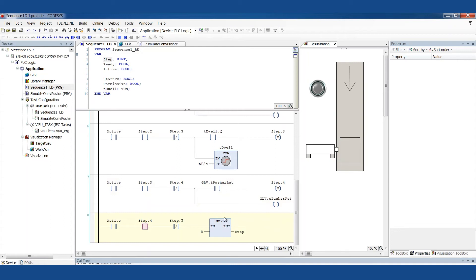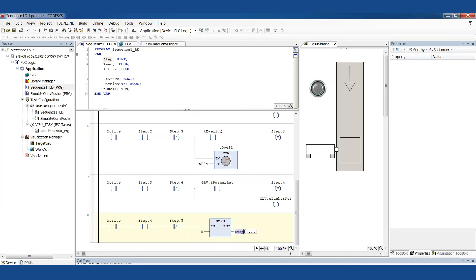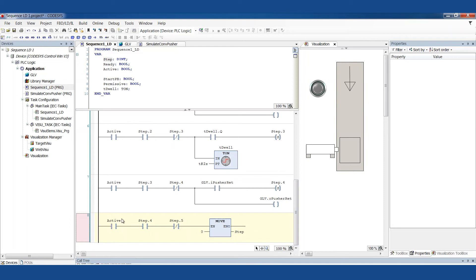In step four, this is another special rung. We're just clearing out the sequence. At the end of the sequence, at some point, we have to say that the sequence is done. We have to clear all of these step bits because we've just been setting them. We haven't been resetting them. The move instruction is assignment. It means I'm going to take this thing and put it into this thing. I'm going to set step to equal zero. And that means we're also clearing out all these bits because all these bits are part of step, that dint.